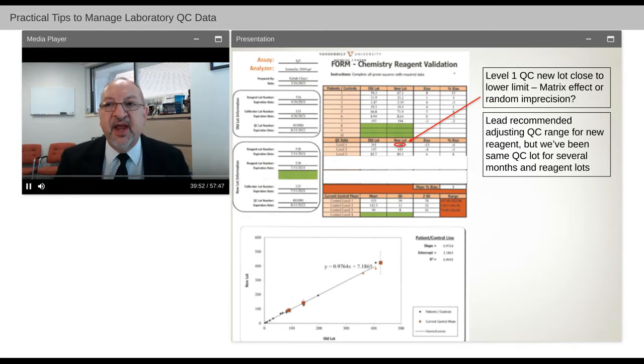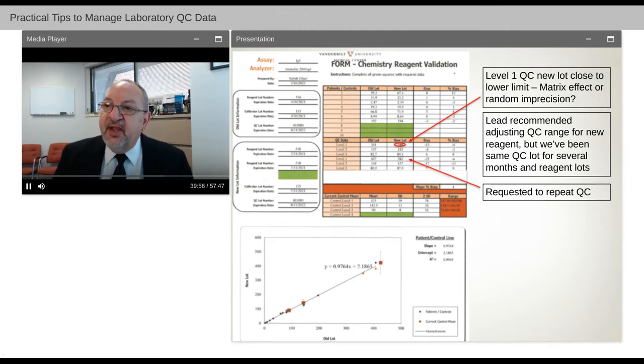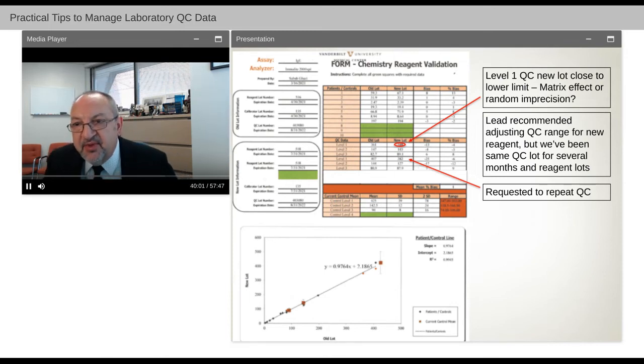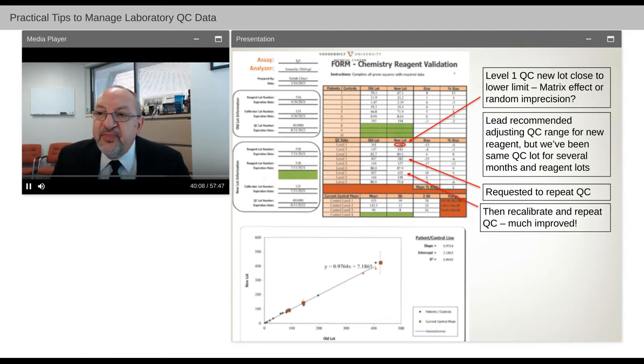Well, because they only ran this once, I requested that they go back, repeat the QC. This time it came up much closer, 382, towards the mean of 425 that we have set. And then to recalibrate and repeat QC, and lo and behold, it pops right onto the mean. So it was just an issue of randomly lying almost out, and on repeat, it came much closer to the mean, and then on recalibration, it's right at the mean.